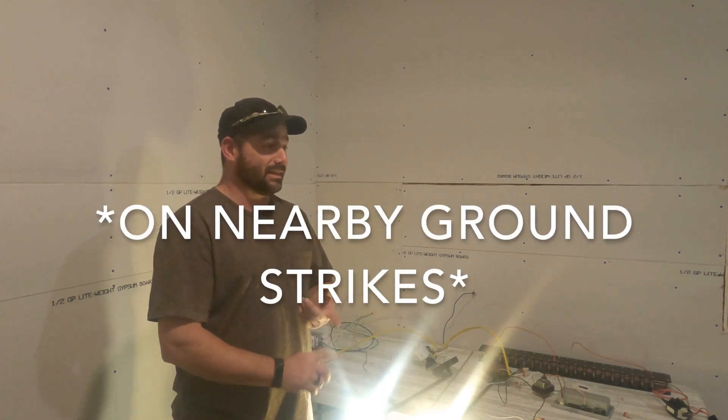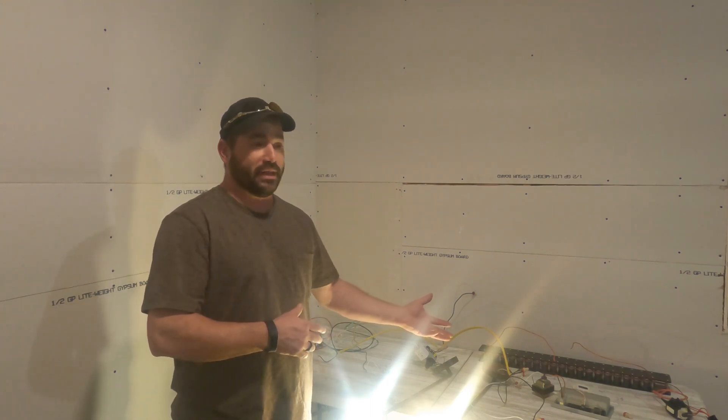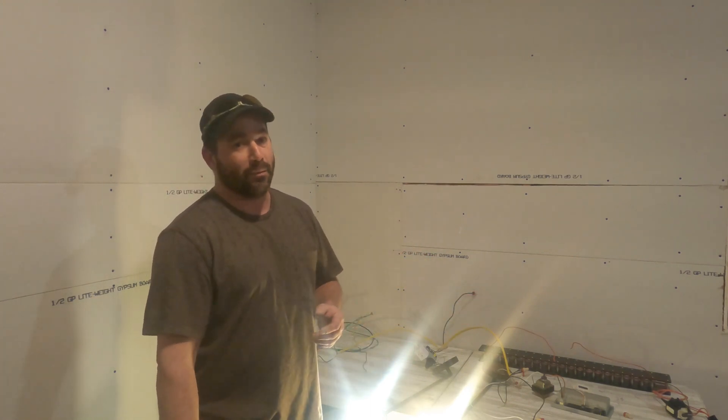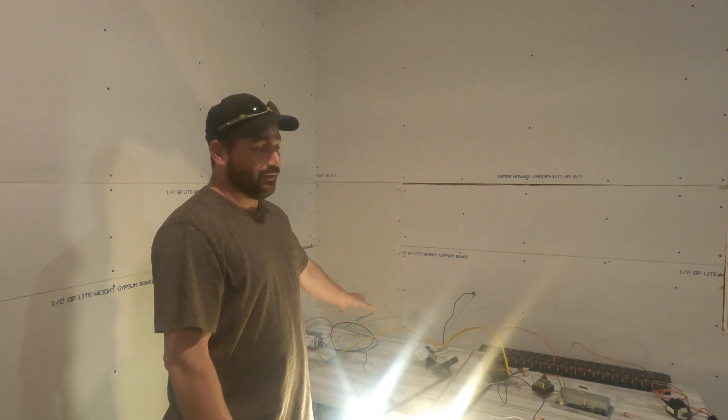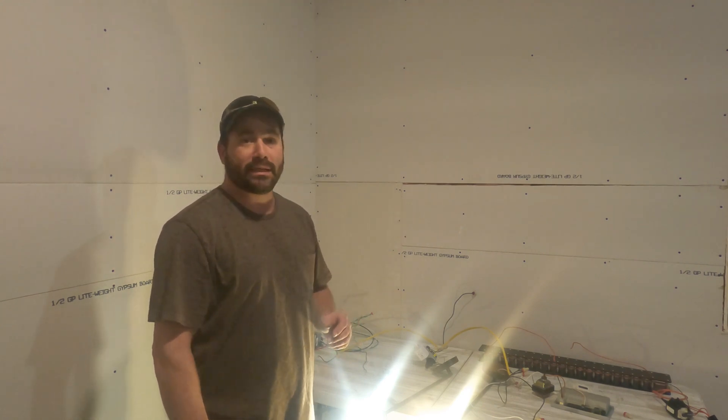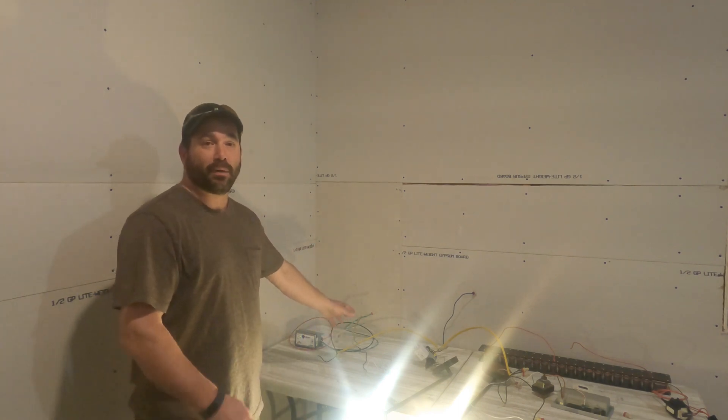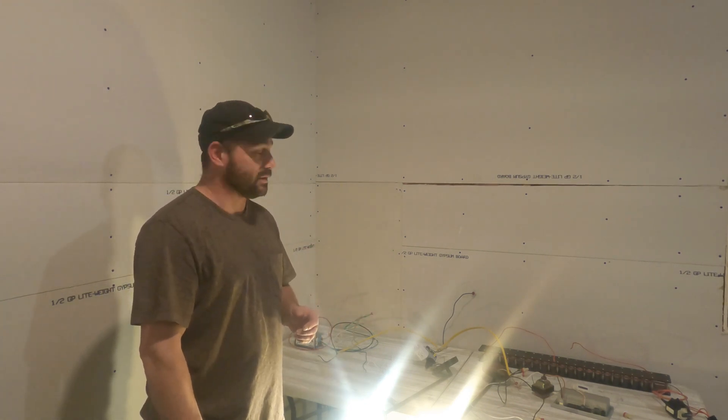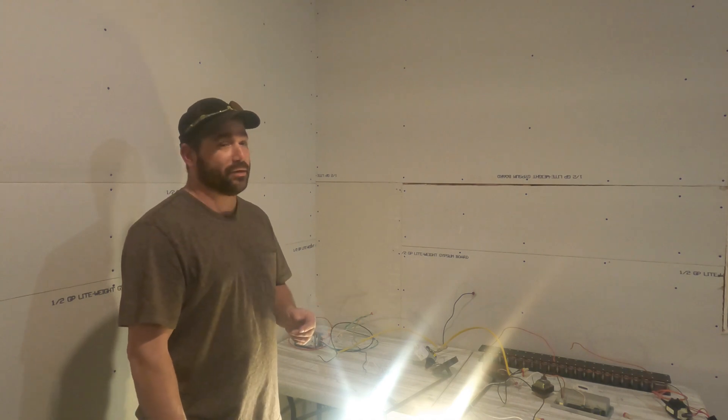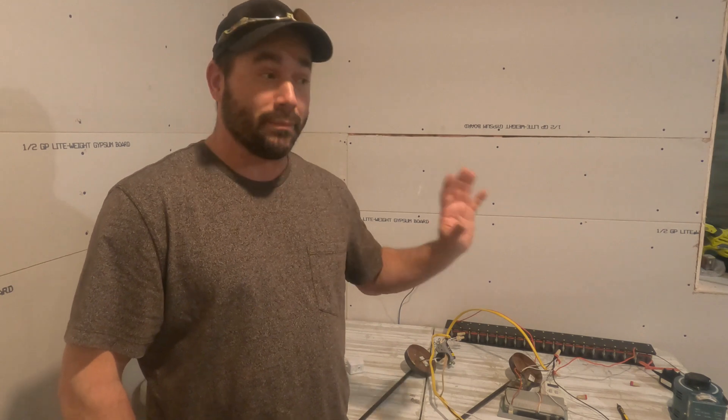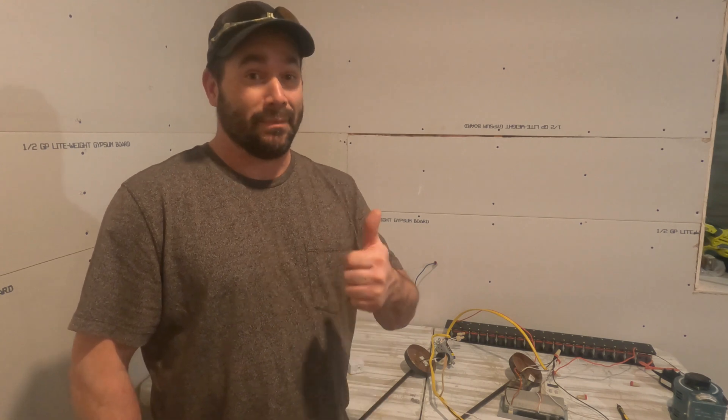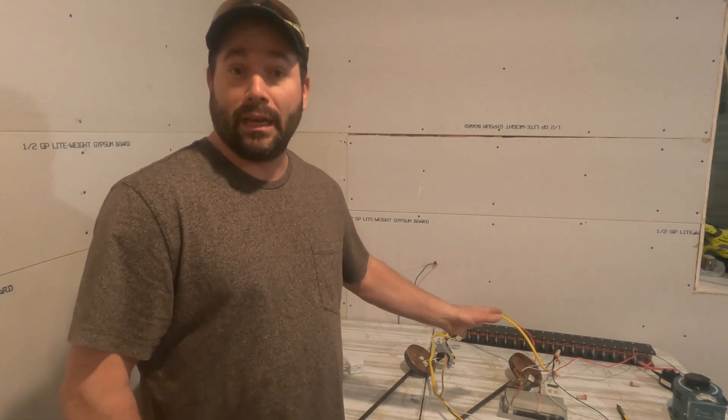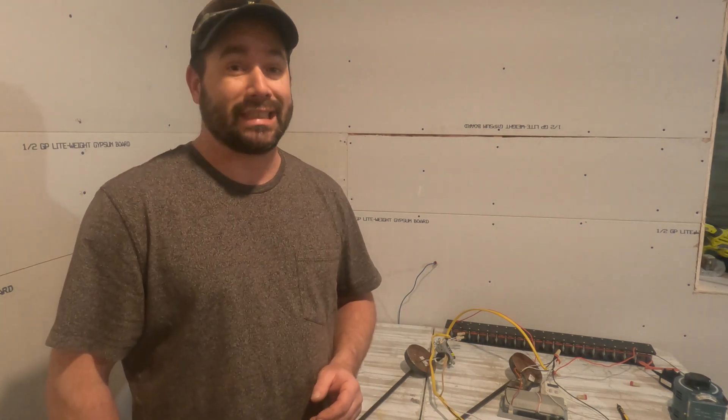Lightning strikes, you'll have an excess of 4,000, 5,000, 6,000 amps. But the voltage could be anywhere from 50,000 hitting the ground up to a million if it was a direct strike onto your conductors. There is a story online of one of these having a direct lightning strike to the grid on a pump station. So this is a city pump station. It completely melted down the EMP shield, but everything that it was connected to, so that panel and everything downstream was just fine. All the pumps survived. And something like that would typically melt down those windings. I can tell you after taking 360,000 volts that I'm really impressed with this EMP shield. Everything seemed to hold up just fine. It didn't blow up. It didn't melt down. I'm giving that a thumbs up right there. We didn't lose any equipment, so that's kind of cool too. And I would say this was a successful run.